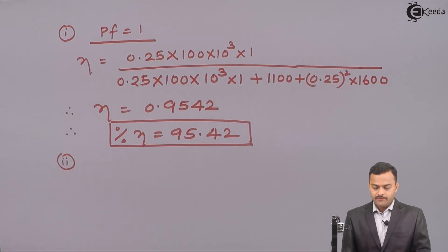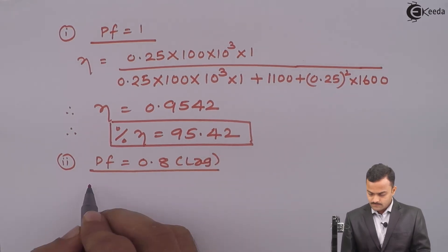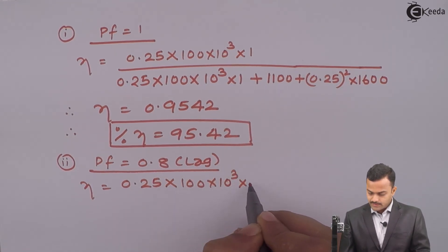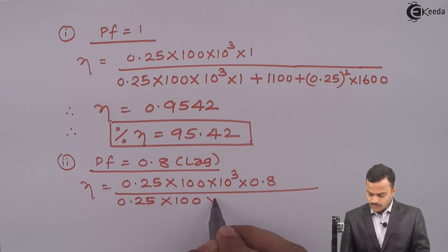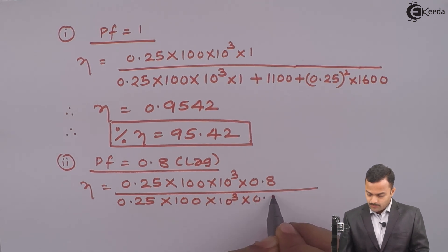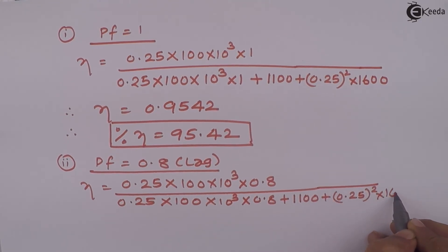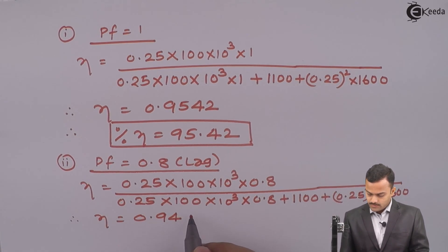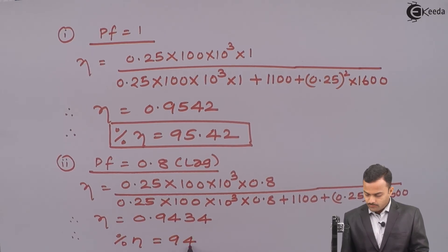Similarly, I can get efficiency at power factor 0.8 lagging. It is 0.25 multiplied by 100 into 10³ times power factor 0.8 upon 0.25 multiplied by 100 into 10³ multiplied by 0.8 plus 1,100 iron loss plus 0.25² times copper loss 1,600. If you solve, you will get efficiency 0.9434. In percentage, it is 94.34%.